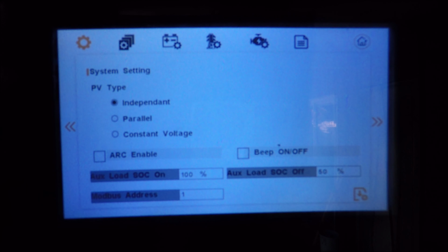Arc enabled. So the arc enabled setting is used to detect DC arc faults in your array, primarily from solar panels, maybe bad connections on your MC4 connectors. In some areas, arc enabled is required by code. Now, challenges can arise from enabling arc detection if you have a lot of lightning, thunderstorms in your area, if there's grounding issues, or if you have different soil moisture levels. Soil saturation can affect the conductivity of the soil, and if the soil is highly conductive, the inverter could detect voltage spikes from other grounded devices in the soil. Keep that in mind and check your local codes if you need to enable arc detection.